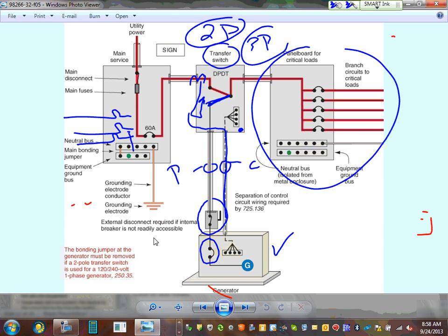Dollars. It costs you more. It's the only reason why we don't in the residential. In commercial, we can. The commercial project that you guys are going to do with your friend is going to have an auto transfer switch. We're going to bring the generator to the auto, the utility to the auto, and out to the building. So if you lose the power, the generator will start and pick up every single load inside your building.